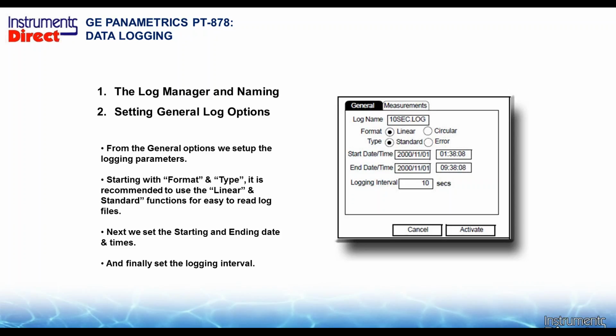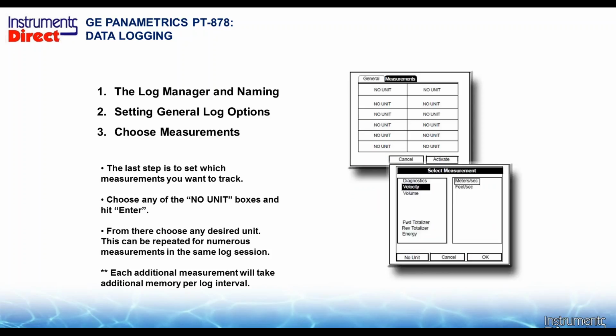And the next step is, how much data do I want to take? So every time you log an interval, it takes a snapshot of data. So remember, you only got 100,000 data points there. If I'm going to leave it there for a month, you need to go backwards to calculate what you're going to log and how often. You could have too much data. So if you have a rapid changing application, do a 10-second log. 95% of all the flow survey logs that I see are usually logged at 1-minute intervals. Again, it's all a function of the number of logs that you have.